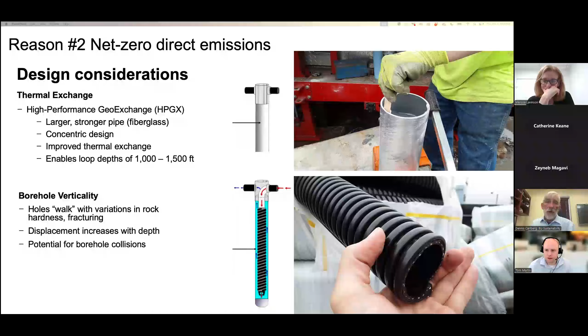We needed to go 1,500 feet deep into the ground to reach the thermal capacity needed in this dense urban environment. So we didn't have a lot of space to do 500 or 800 foot deep bores. We're using a concentric system rather than the typical HDPE U-bends. And just to note, the bedrock on campus is about 200 feet below the surface. So we needed to go deep really just to get to a high performance bedrock.